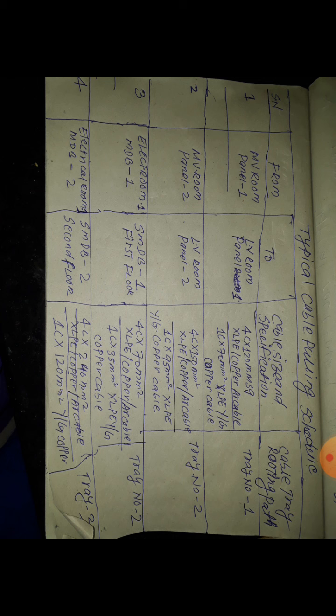The yellow green earthing needs 1 core into 35 mm square. So you see there is a 70 mm square cable, and 35 is also available. This is the half value: 35 into 2 is equal to 70. So if the same sizes are available, you can use the half value in the same sizes. Okay, so this is the system. This goes to tray number 2. All are given like that, and anybody can see it in the drawing.